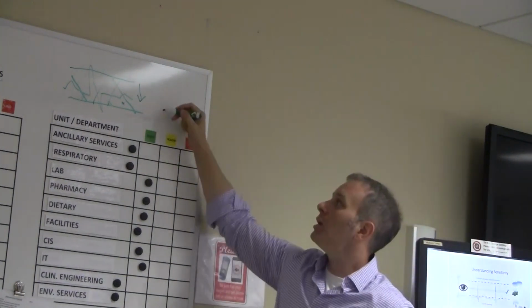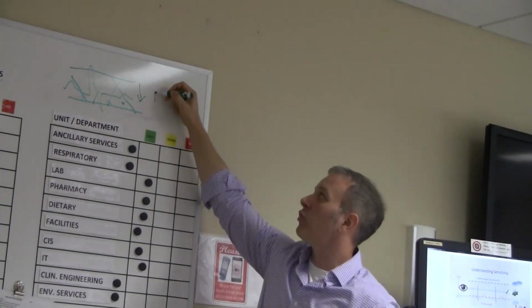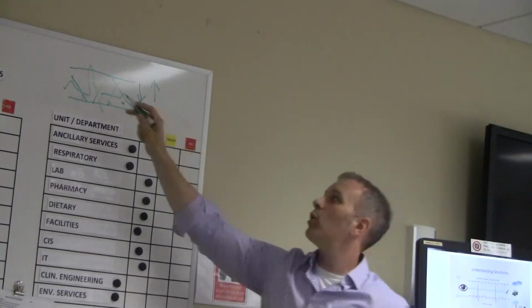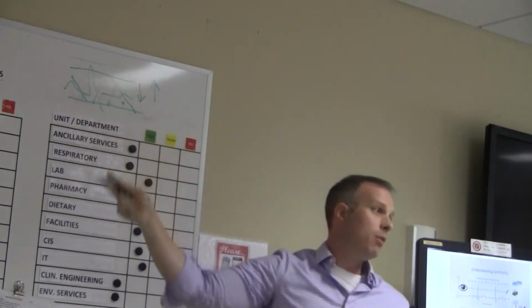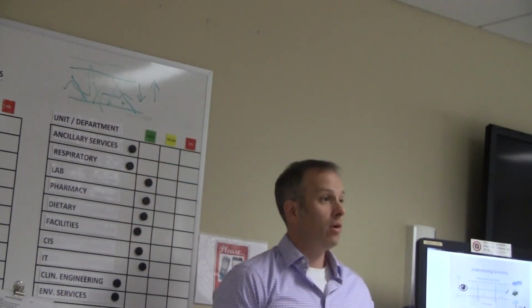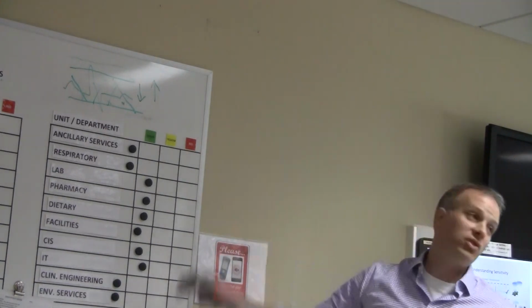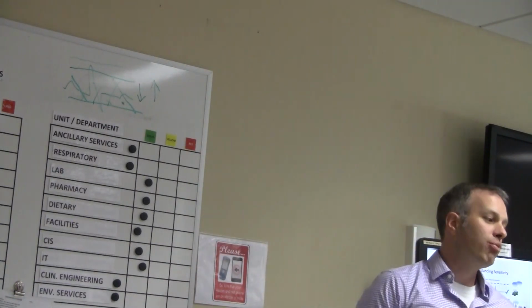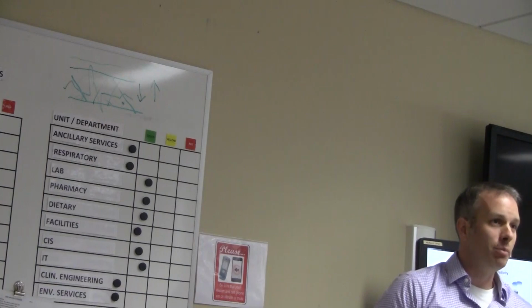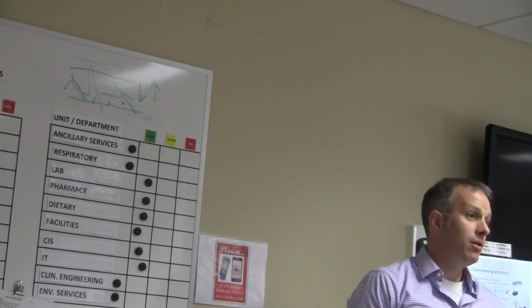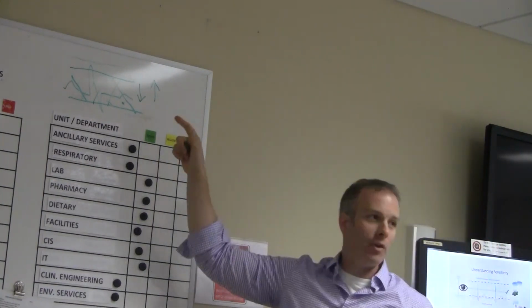Then I want to decrease the sensitivity, which means raise the number, okay? So I can get to the point where it doesn't see anything. Even though the heartbeat is there, it's not seeing it at all, okay? Or I can drop it so low that you can have problems: if you jiggle the wire a little bit, it will think that's its heartbeat as well. So you want kind of a perfect range.